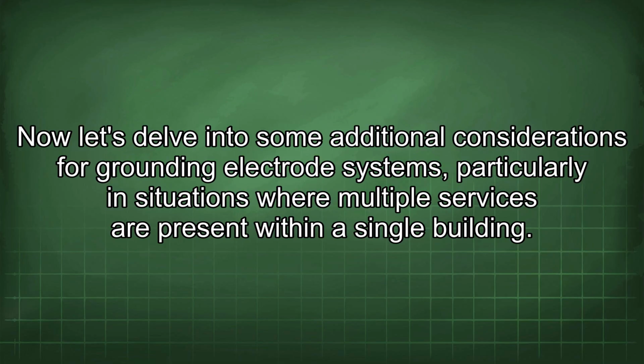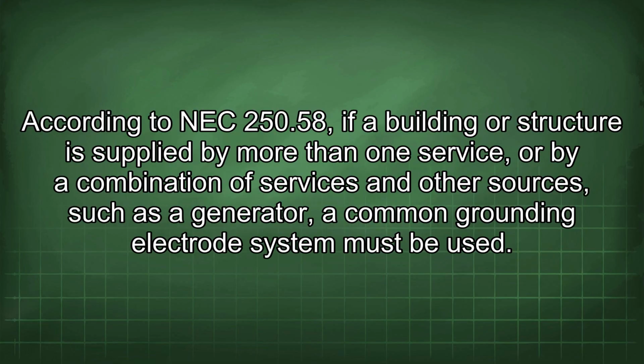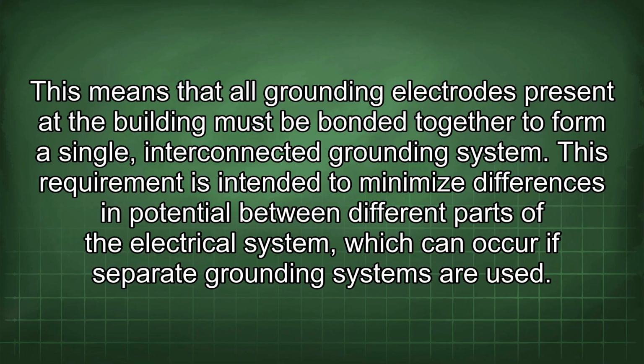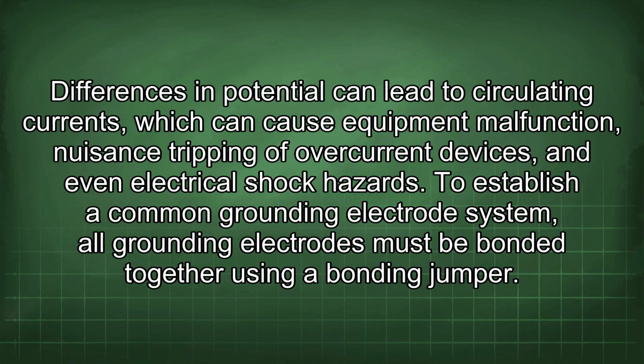Now let's delve into some additional considerations for grounding electrode systems, particularly in situations where multiple services are present within a single building. According to NEC 250.58, if a building or structure is supplied by more than one service, or by a combination of services and other sources, such as a generator, a common grounding electrode system must be used. This means that all grounding electrodes present at the building must be bonded together to form a single, interconnected grounding system. This requirement is intended to minimize differences in potential between different parts of the electrical system, which can occur if separate grounding systems are used. Differences in potential can lead to circulating currents, which can cause equipment malfunction, nuisance tripping of overcurrent devices, and even electrical shock hazards.